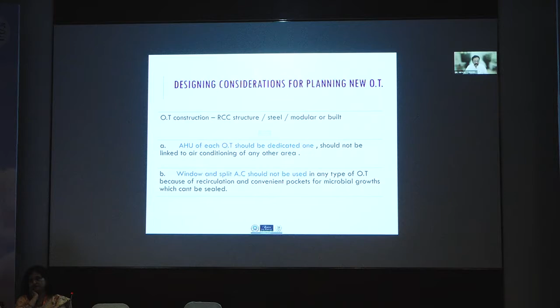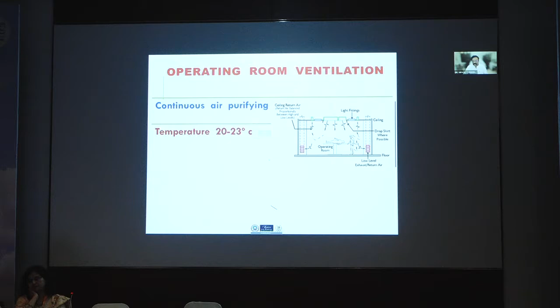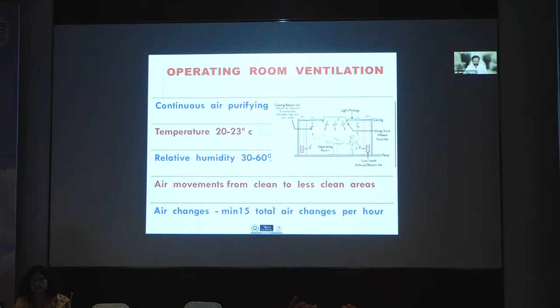For ventilation requirements, there has to be continuous air purifying if you have an AHU unit. The ideal temperature in the operation theatre is 20 to 23, relative humidity is 30 to 60, or 55 plus or minus 5. Air movement has to be from clean to less clean areas, and air changes must happen at a minimum of 15 total air changes per hour. So basically, operation theatre design requirements are a legal requirement.